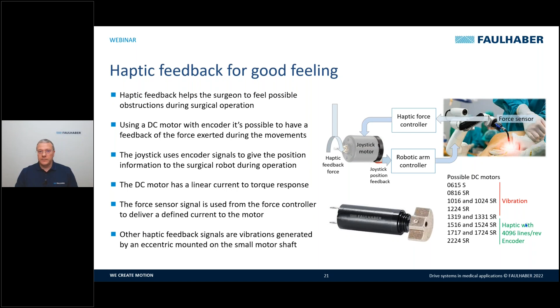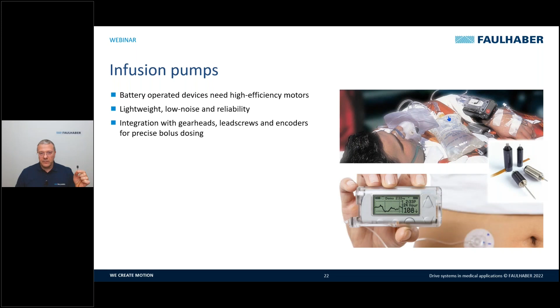Another interesting application is the field of infusion pumps. Infusion pumps typically use battery operated devices, so it's important to have a high efficiency motor. We can get over 90% of efficiency. They must be light, with low noise and high reliability. The possibility to use integration with a gearhead, lead screw, and encoder for precise drug dosing is important. And we can use DC motors, brushless motors or stepper motors in diameter size from 6 to 10 millimeter for the stepper motor, and 12 or 13 millimeter for brushless and DC motors.